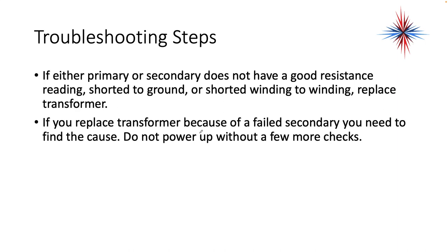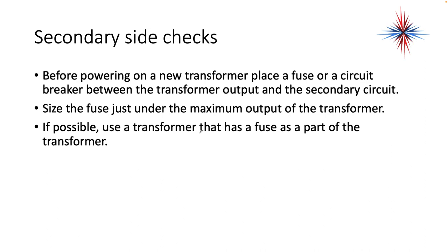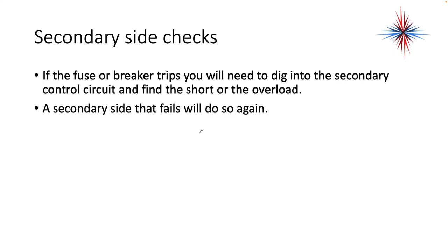If either the primary or secondary does not have good resistance readings — shorted to ground or shorted winding to winding — replace the transformer. If you replace the transformer because of a failure on the secondary side, you need to find the cause; do not power the system up without further checks. Before powering on a new transformer, place a fuse or circuit breaker between the transformer output and the secondary circuit, sized just under the maximum output of the transformer. If possible, use a transformer that has a fuse or breaker built in. If the fuse or breaker trips, dig into the secondary control system and find the short or overload. A secondary side that fails will do so again because there's a problem somewhere — these don't fail on their own.